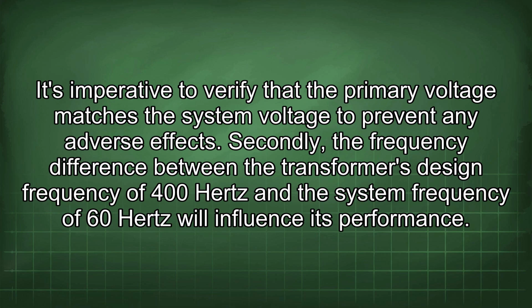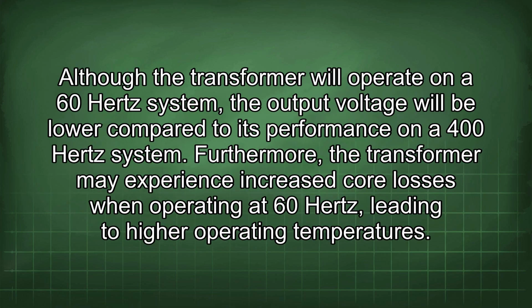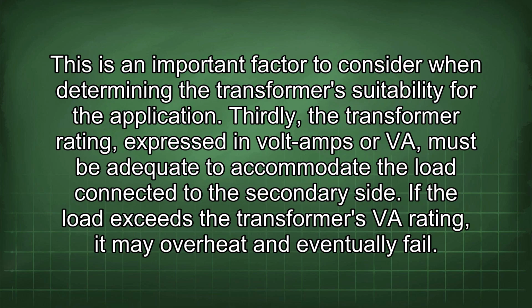Secondly, the frequency difference between the transformer's design frequency of 400 Hz and the system frequency of 60 Hz will influence its performance. Although the transformer will operate on a 60 Hz system, the output voltage will be lower compared to its performance on a 400 Hz system. Furthermore, the transformer may experience increased core losses when operating at 60 Hz, leading to higher operating temperatures. This is an important factor to consider when determining the transformer's suitability for the application.